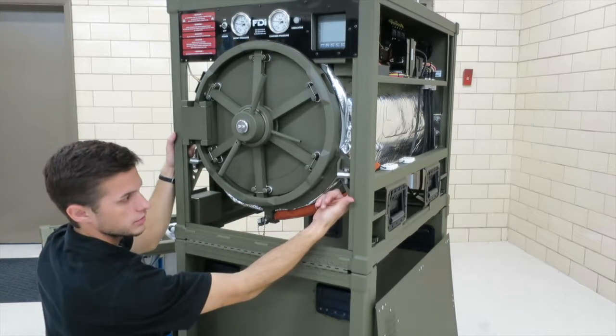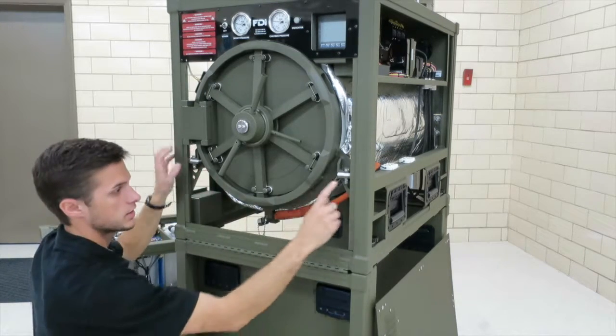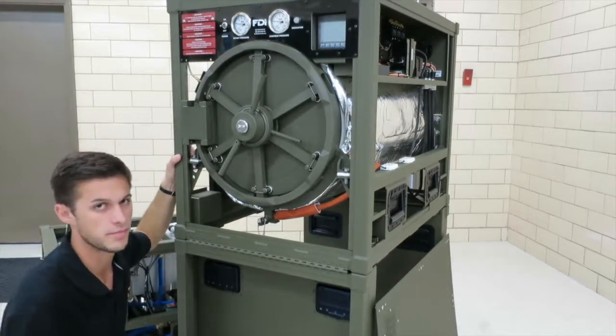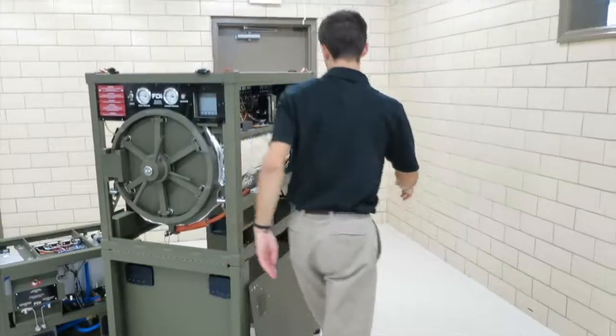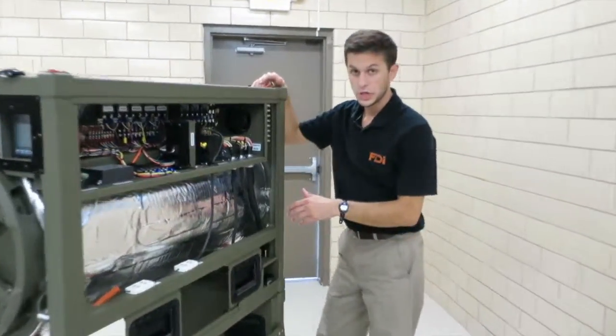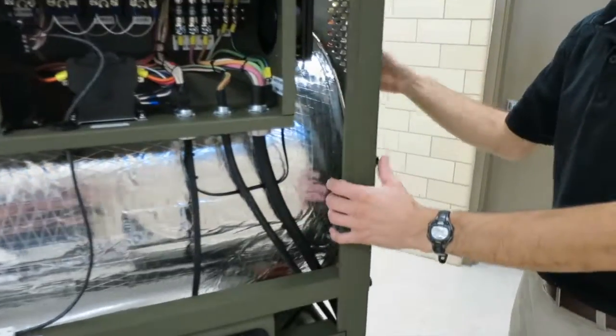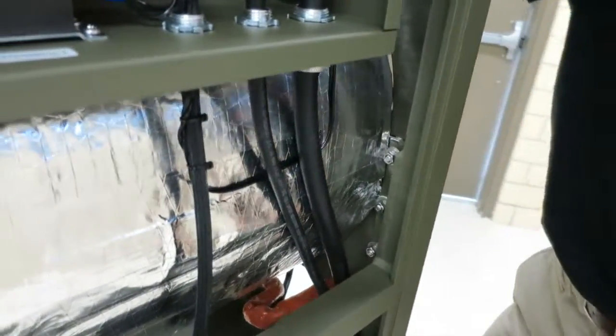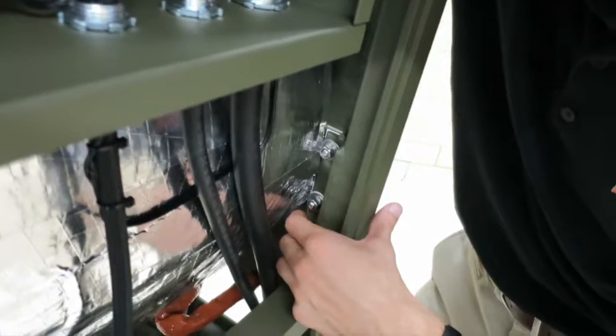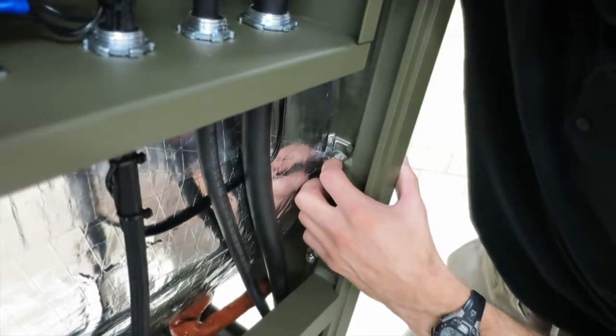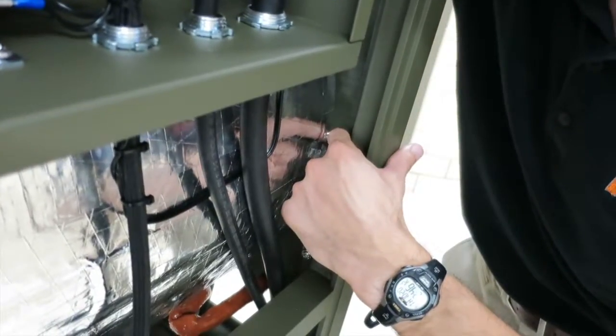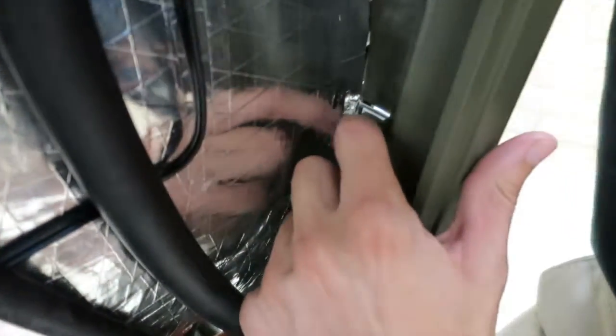And there are bolts in the back on both sides and bolts in the front on both sides. We're going to go around to the back and look at the back chamber mount bolts. So also in the back there are 8 shoulder bolts, and we also have the nuts here too. So you'll see a lock washer. If you look really closely, there's going to be a thermal break pad and then a little thermal washer. Just going to make sure all that stuff is there and intact, and then make sure all these are tight with a wrench. And it's also the same on the other side.